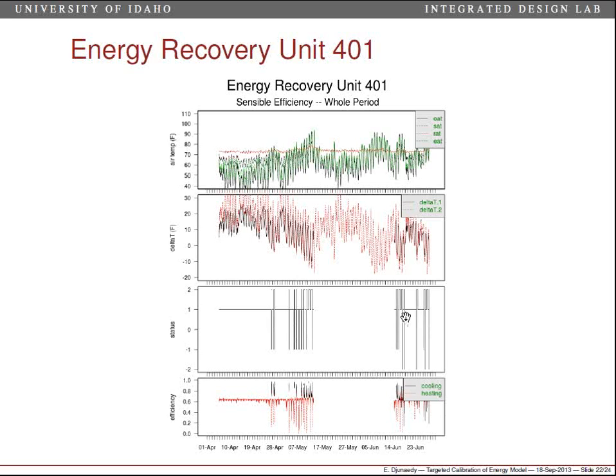So this is the calculation of the actual efficiency, not what's on paper. We measure 4 streams of air and calculate the actual efficiency at each time. We measured the incoming from outside, then the outgoing from the heat recovery, and then the return and the exhaust. We have 2 delta T here, and you see the status. I made this up, but I can identify four statuses of operation for the energy recovery unit, which is not in the manual.